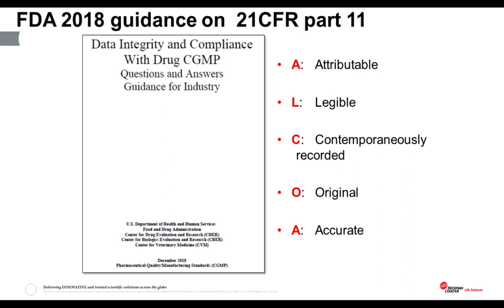In their 2018 question and answers paper on interpreting their data integrity guidance, the FDA introduced for the first time the acronym ALCOA. In response to a question about what a good electronic record looks like, they said it should be Attributable — the first A in ALCOA — to the person taking the sample. It should be Legible, which implies handwriting is probably not the right way to go. It should be made Contemporaneously — at the same time the sample is taken, rather than later from paper printouts. And the record should be the Original record, and the data it contains should be Accurate.